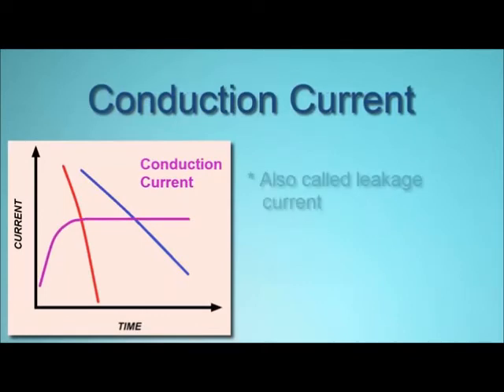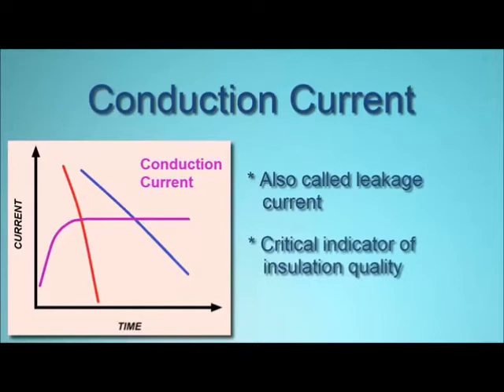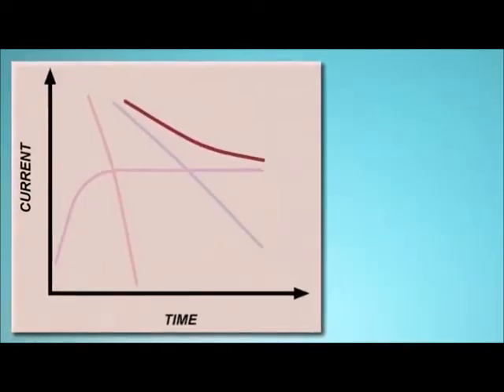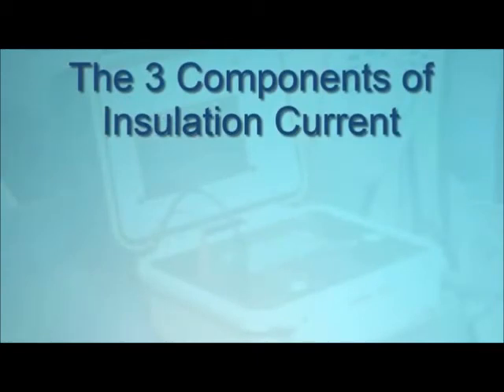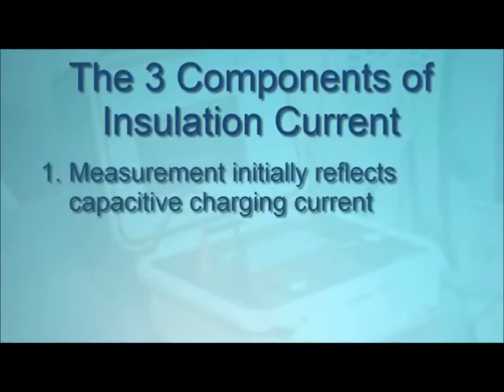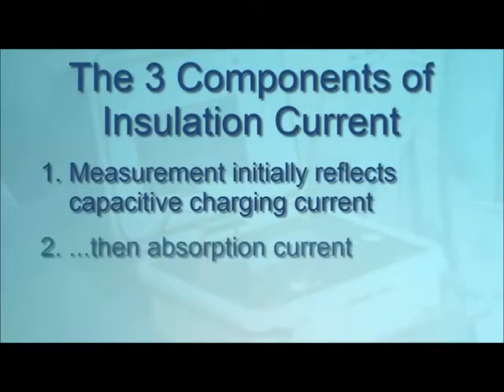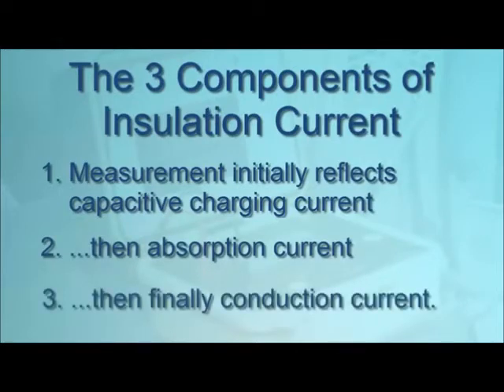Conduction current, often called leakage current, is the steady current present both through and over the insulation. This is a critical measurement, since an increase in conduction current over time is a likely indication of deteriorating or damaged insulation. Combining these three components produces a total insulation current profile similar to the illustration shown on the screen. To summarize: the initial measurement primarily reflects capacitive charging current; after a period of time, absorption current is dominant; and beyond 1 to 10 minutes, the measurement is mainly composed of conduction current — the primary value used to calculate the quality of insulation resistance. Understanding how these individual currents contribute to the total insulator current can help you correctly interpret the results you receive when performing a test.